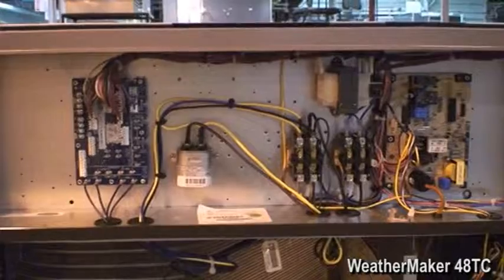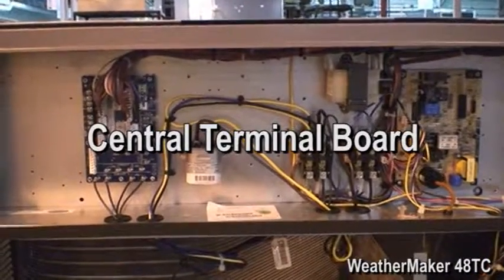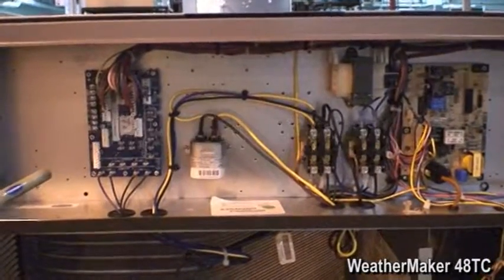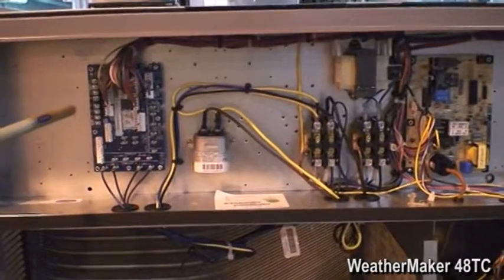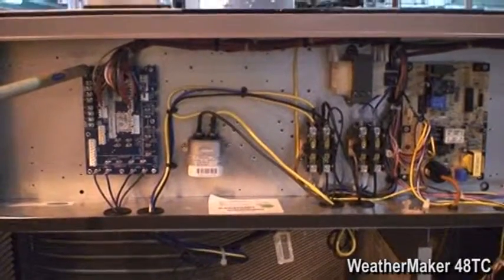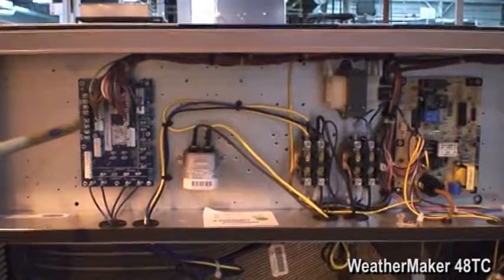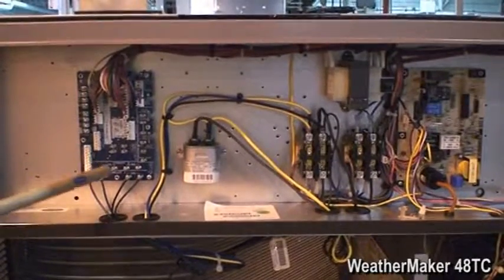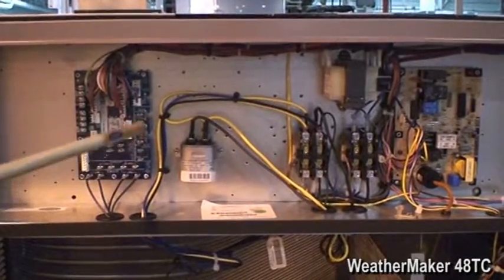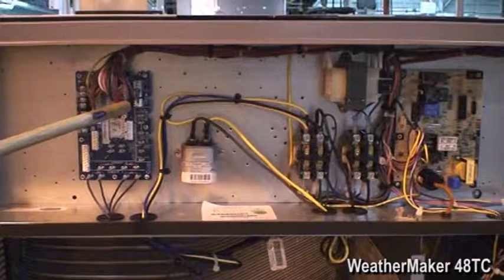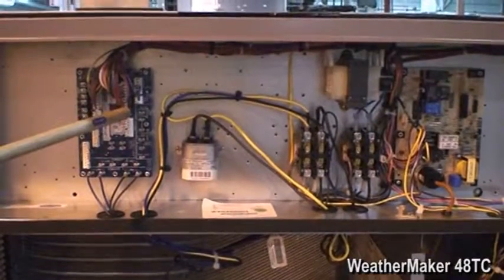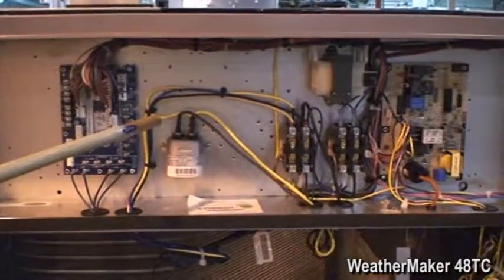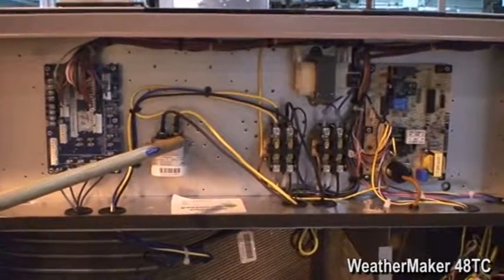Starting on the left is the unit's central terminal board. There is no need for field-furnished wire nuts, just an easy-to-understand terminal board for not only thermostat connections, but also connections for smoke detectors, an economizer, and other required devices needed on jobs. Next on the Carrier unit is the securely fastened capacitor, contactors, and the transformer.